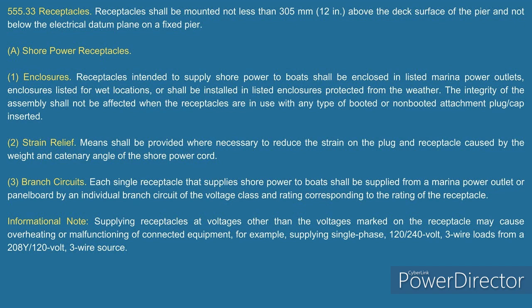Why did they feel the need to go in and say, for an individual branch circuit, being very specific, that it goes to what? Utilization equipment. The reason is because it's hardwired. Now, if you go back and look at the definition of a branch circuit, it says it can go to an outlet or outlets. And if I just go to one outlet, it can just be an individual branch circuit.